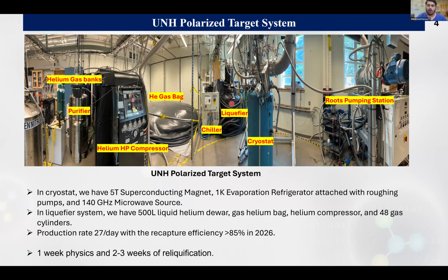There's also a liquefier that provides 500 liters of liquid helium for our experiments, a helium gas bag to capture the boil-off from the cryostat, and a helium compressor to compress the gas from this bag into 48 gas cylinders.